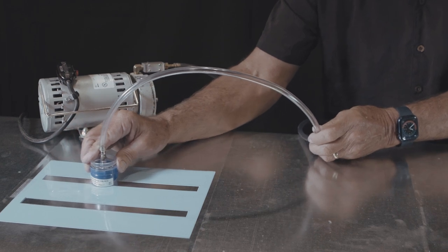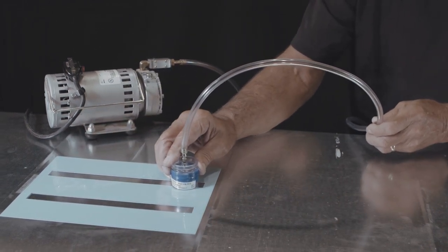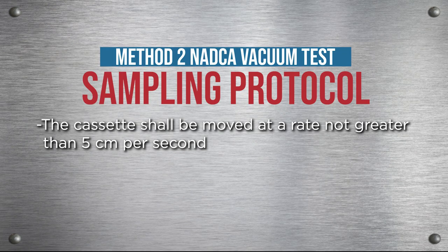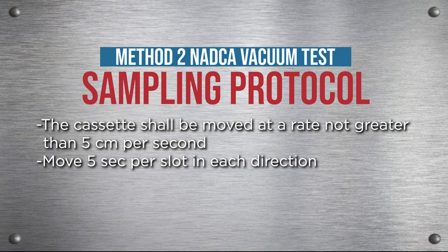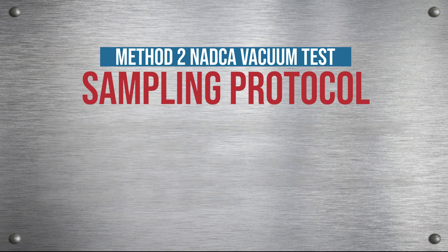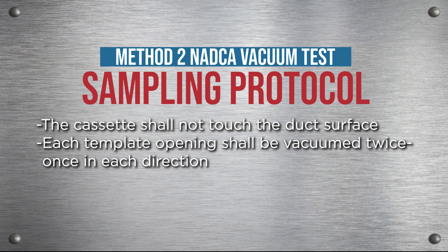Vacuum the open area of the template by sliding the cassette from one end of each template opening to the other. The cassette shall be moved at a rate not greater than 5 centimeters per second, 5 seconds per slot in each direction. The edges of the cassette shall always rest on the template. The cassette shall not touch the duct's surface. Each template opening shall be vacuumed twice, once in each direction.